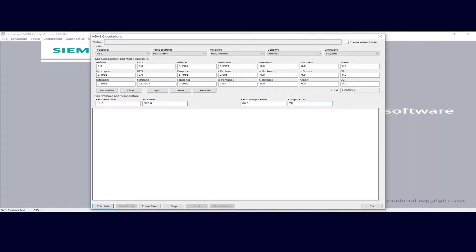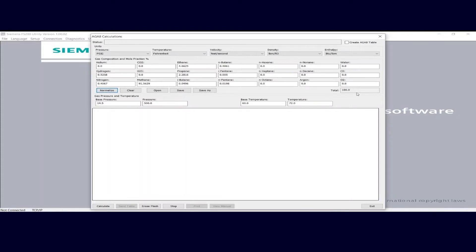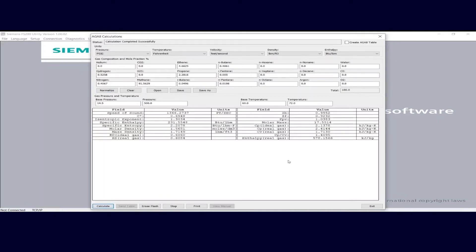We can now begin entering our gas mole fractions. Just to save a little time, I'll speed up the tape for this portion. With your mole fractions entered, you can now generate your enthalpy calculations. Verify your base pressure and your actual pressure, your base temperature and your actual temperature. Then click the normalize button, which will round the gases off to give you exactly 100%, then come down to the bottom and click Calculate.